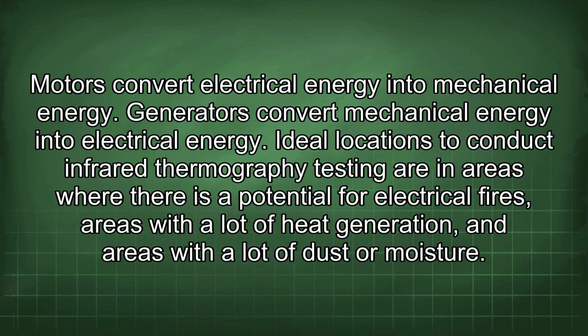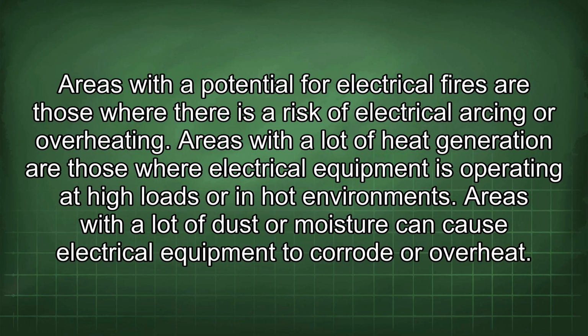Ideal locations to conduct infrared thermography testing are in areas where there is a potential for electrical fires, areas with a lot of heat generation, and areas with a lot of dust or moisture. Areas with a potential for electrical fires are those where there is a risk of electrical arcing or overheating. Areas with a lot of heat generation are those where electrical equipment is operating at high loads or in hot environments. Areas with a lot of dust or moisture can cause electrical equipment to corrode or overheat.